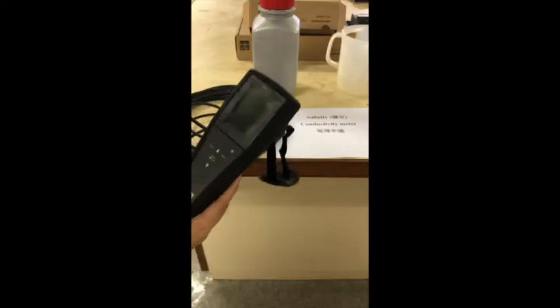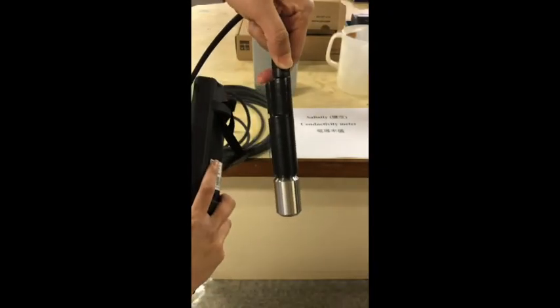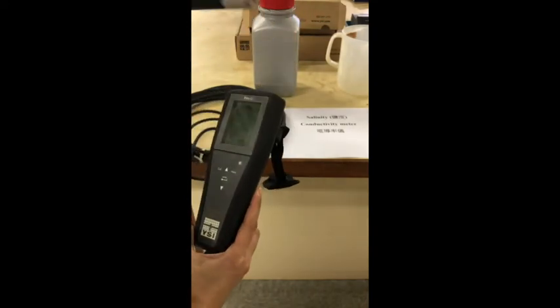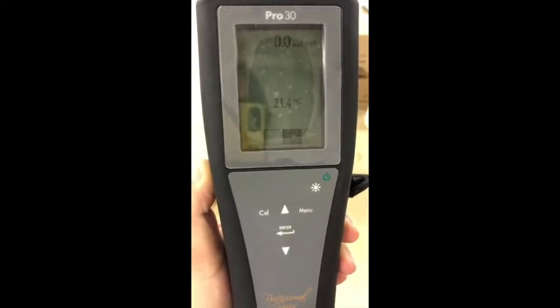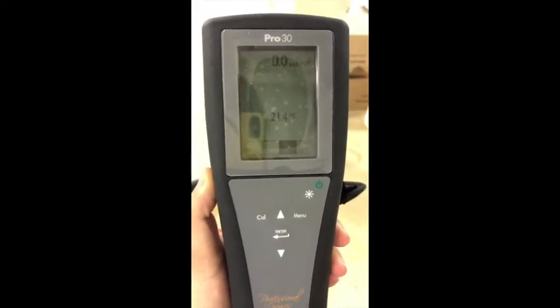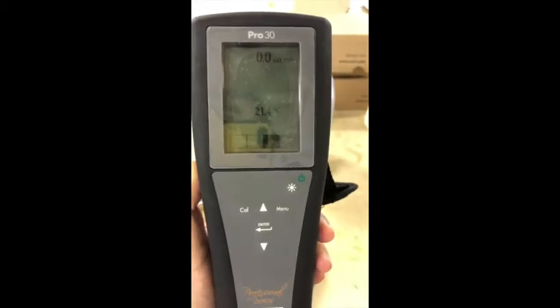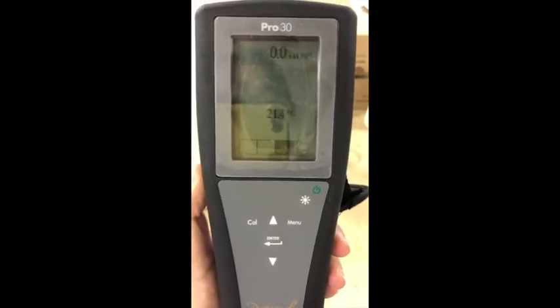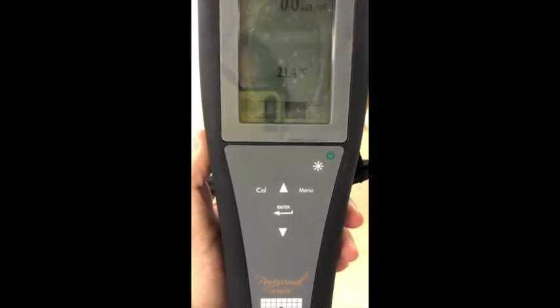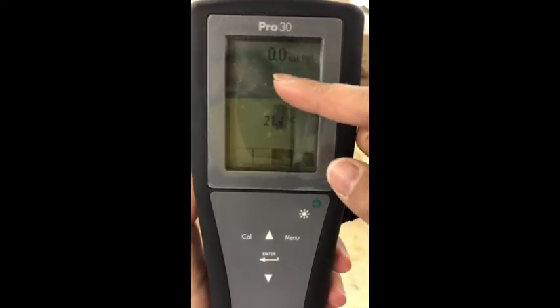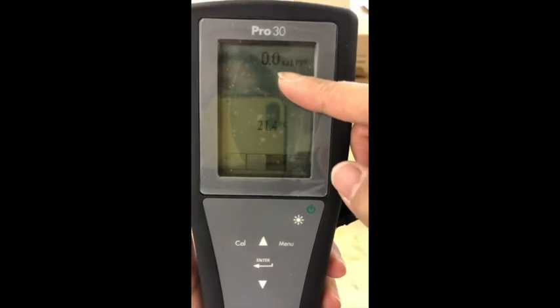And let me introduce the conductivity meter. This is the control panel. And this is the probe for measuring the conductivity. When proceeding with the calibration process, press the CAL button. It will change the mode to calibration. As mentioned before, the electrode is stable, so the routine calibration is not required. The functions of a conductivity meter are not limited to measuring the salinity. You can change the mode by pressing the mode button to measure other parameters. And now is the mode for measuring the salinity.